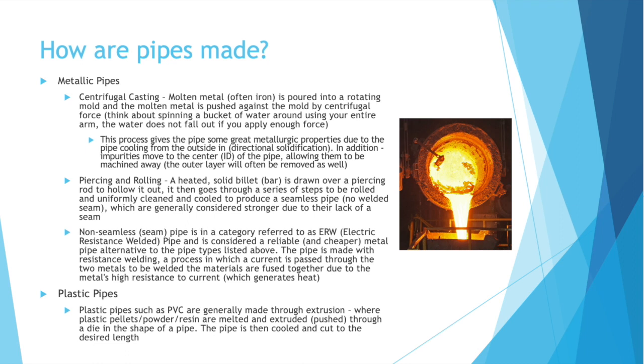You also have piercing and rolling, where a heated solid billet — a bar — is drawn over a piercing rod to hollow it out. It then goes through a series of steps to be rolled and uniformly cleaned and cooled to produce a seamless pipe. Seamless pipes are generally considered stronger than seamed pipes due to their lack of a seam. Non-seamless pipe — pipe with a seam — falls under ERW, electric resistance welded pipe, and is considered a reliable and cheaper alternative. The pipe is made with resistance welding, where a current is passed through the two metals, and due to the metal's resistance to current, heat is generated, fusing the materials.